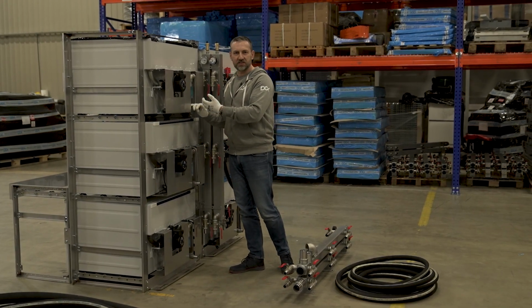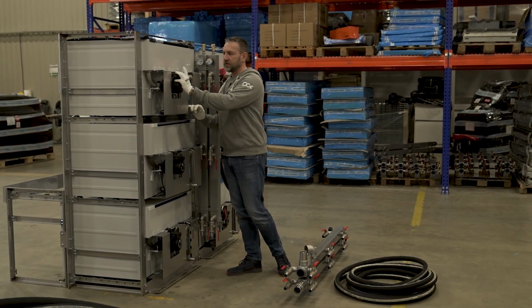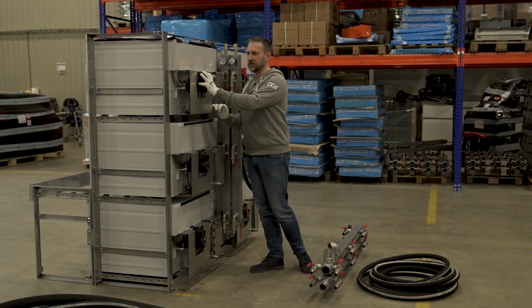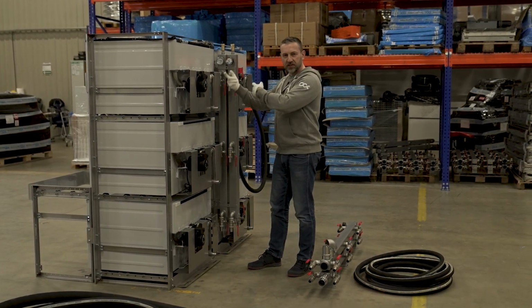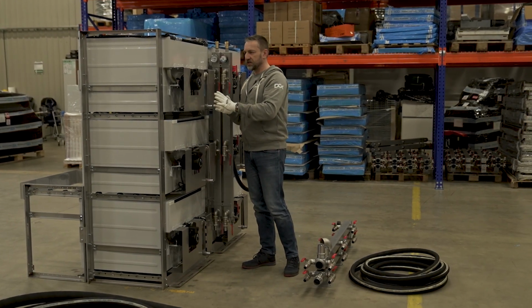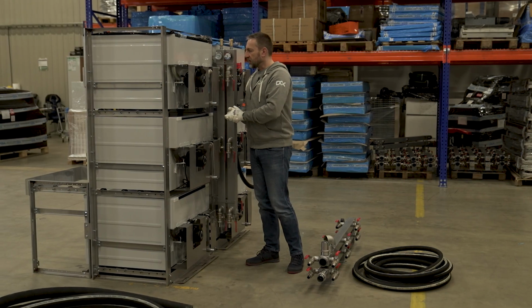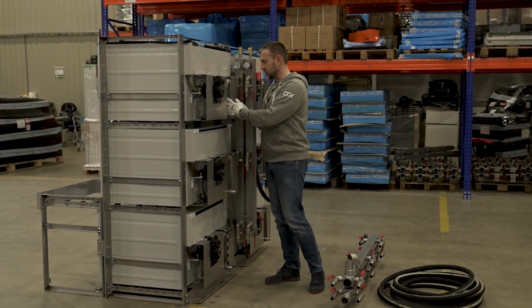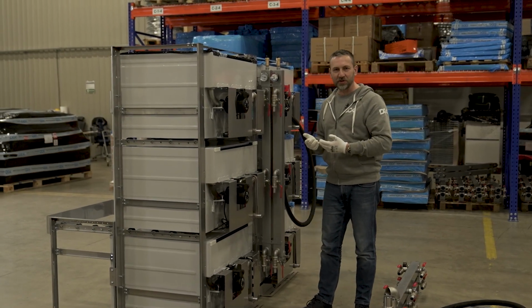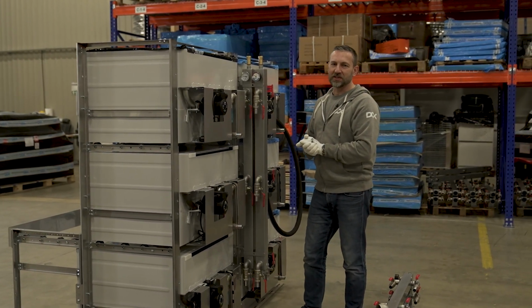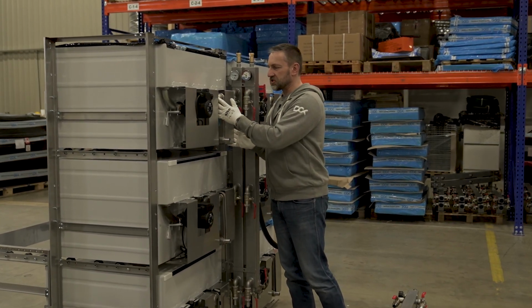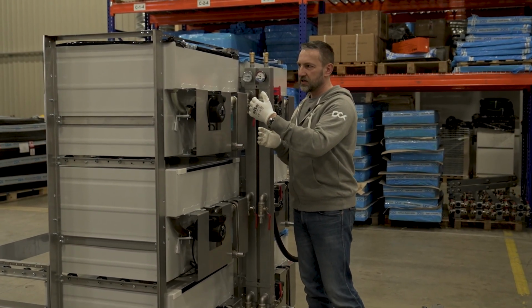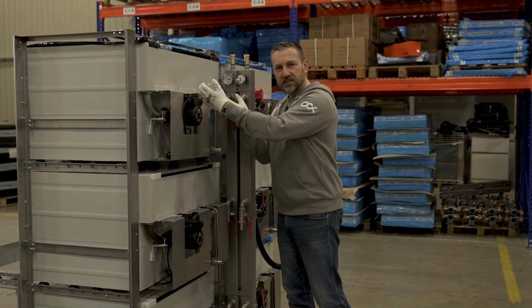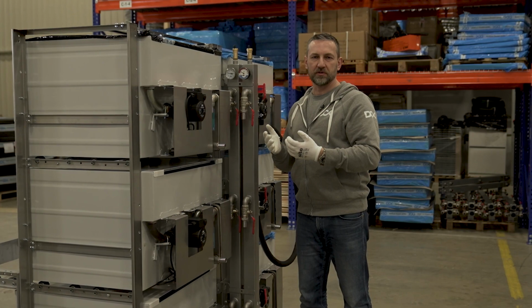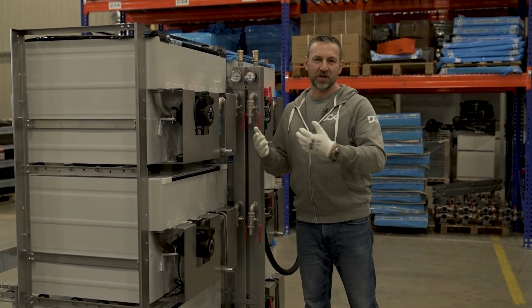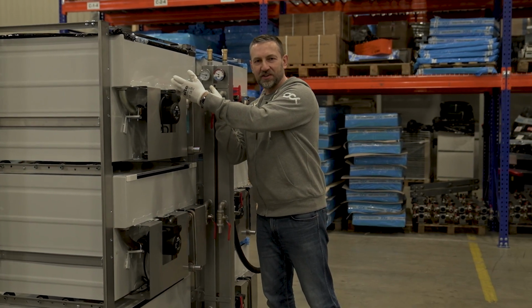These are actually smart tanks, or active tanks. Those tanks have a circulation pump, which circulates the fluid inside of that enclosure. That fluid doesn't leave the enclosure, it just circulates internally. And we have a heat exchanger, which we right now oversize for the bigger one, trying to catch up with the rising densities of immersion cooling systems. That heat exchanger exchanges the heat between the dielectric fluid inside and the water or water-glycol mixture on the outside, so the primary loop outside and the secondary loop inside.